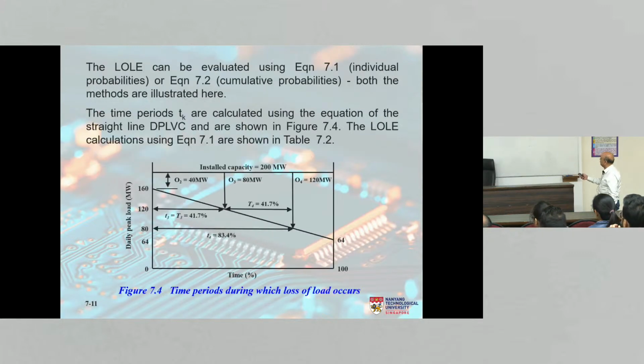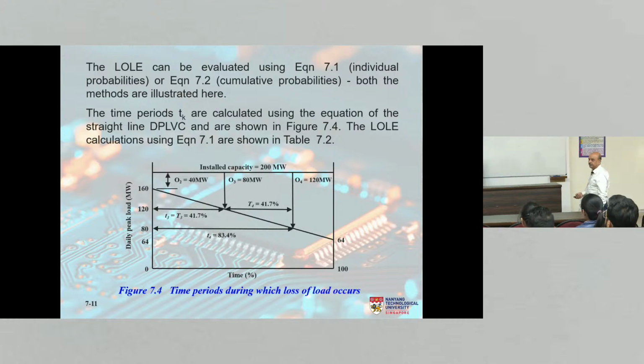So we use 7.1 or 7.2. You can use both individual and cumulative probabilities. So I just want to illustrate using this graph again how the calculations are done. So our installed capacity is 200 megawatt. Our peak load is 160 megawatt, correct? Installed capacity is 200, five generators of 40 megawatt each, and the peak load is given as 160 megawatt. So if none of the generators is out, we have 200 megawatt, we are able to meet the load, right? So there is no loss of load, correct?